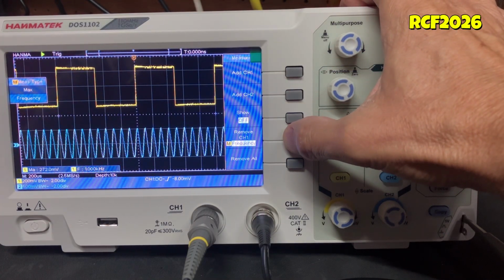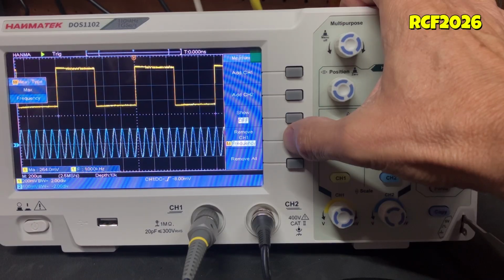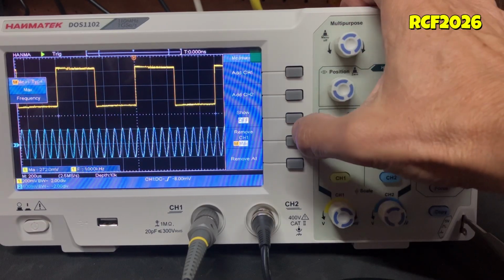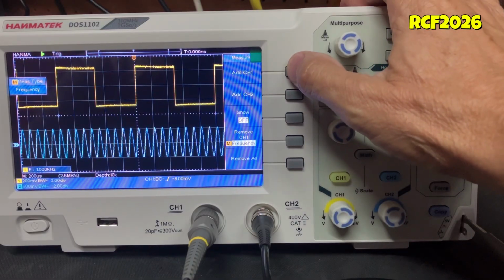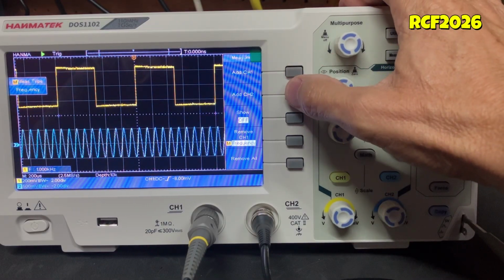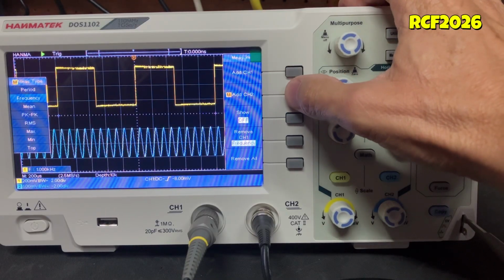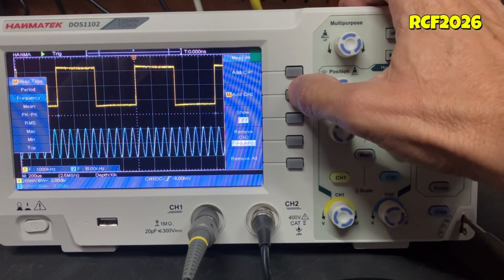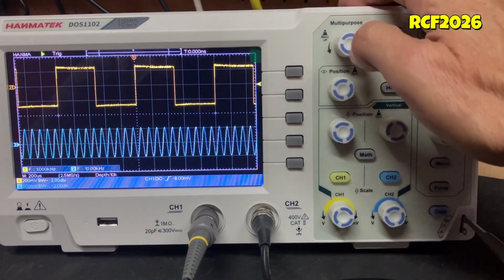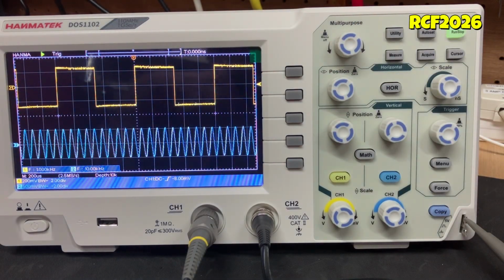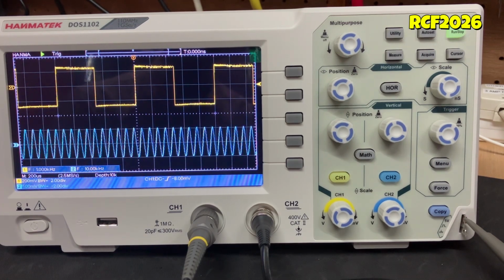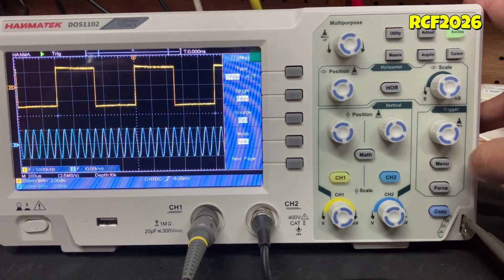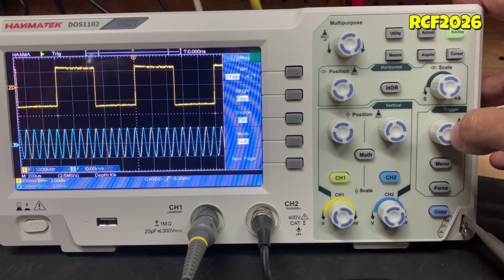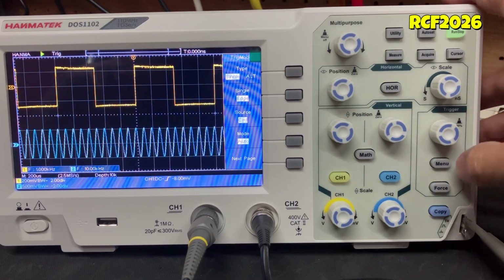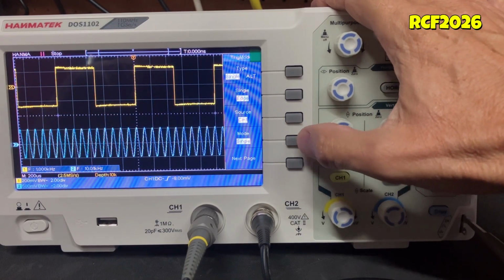It is important to remember that if you move the trigger level outside the voltage range of the selected input signal, the oscilloscope may no longer be able to trigger correctly and the waveform can become unstable or start moving across the display. Simply move the trigger level back within the waveform until a stable display is obtained. You can also experiment by changing the trigger source between channel 1 and channel 2 to see which signal provides the most stable trigger. This can be particularly useful when the two input signals have different frequencies or waveform characteristics.